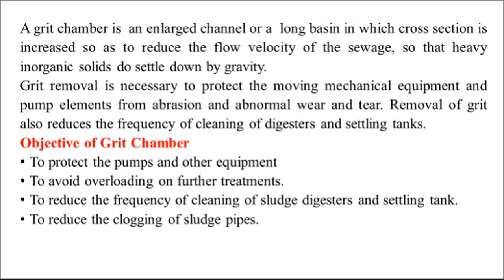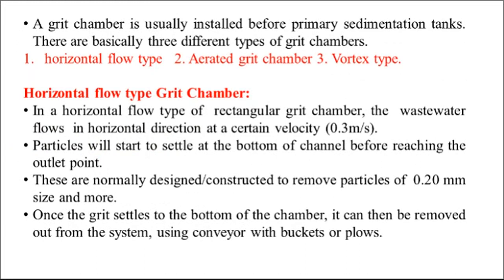The main objectives of grit chambers are: first, to protect the pumps and other equipment. Second, to avoid overloading on further treatment units. Third, to reduce the frequency of cleaning of sludge digesters and settling tanks. And the last objective is to reduce the clogging of sludge carrying pipes. A grit chamber is usually installed before the primary sedimentation tank.